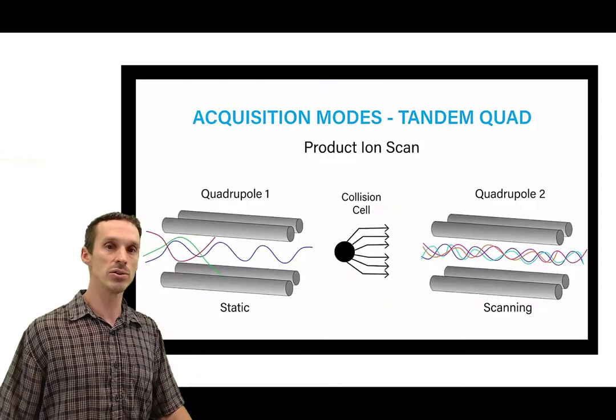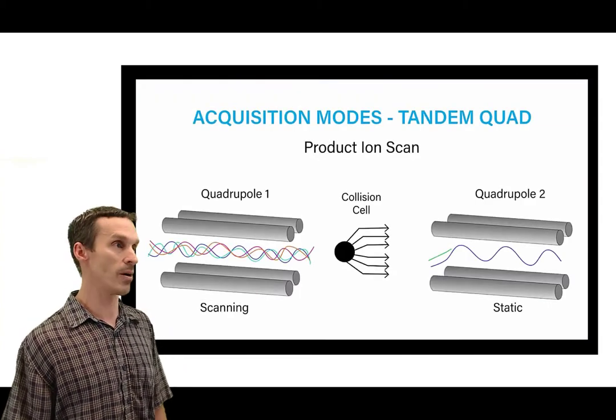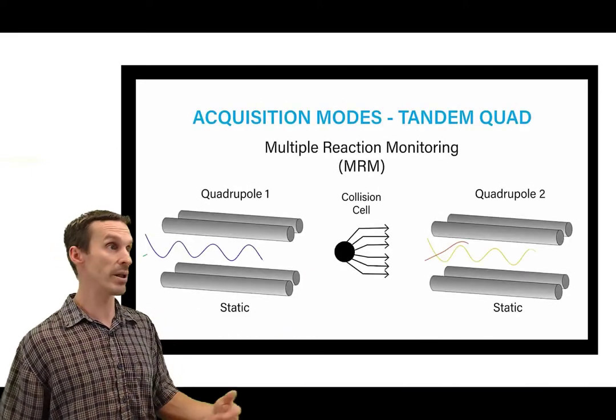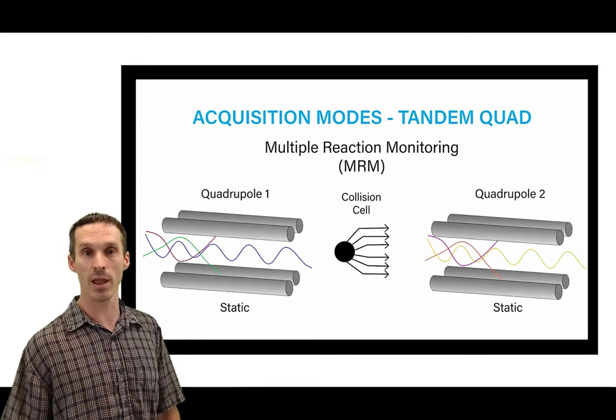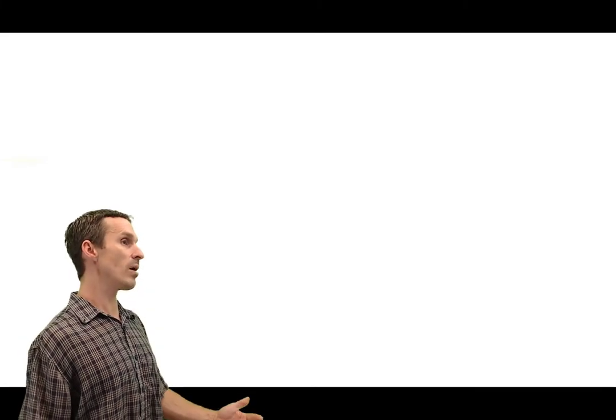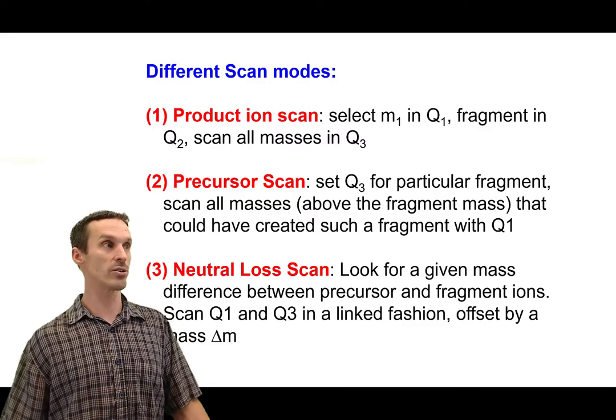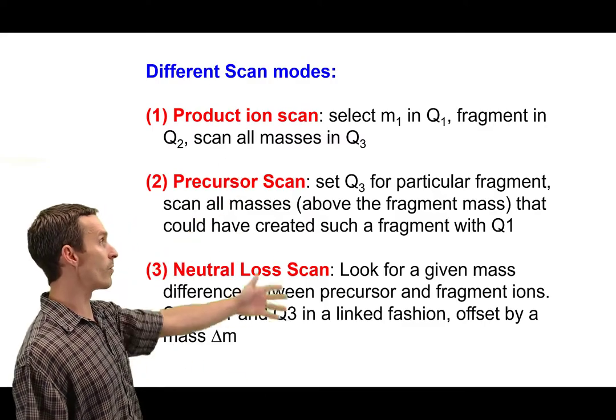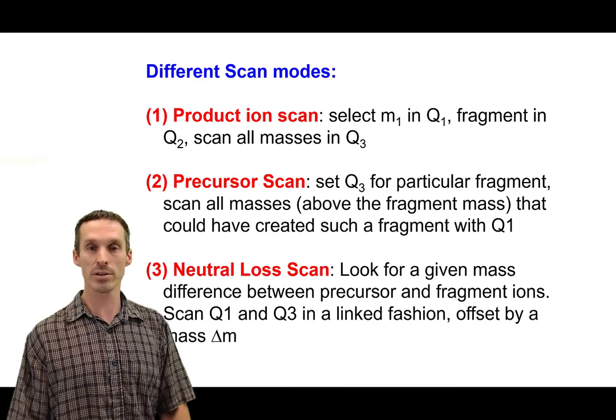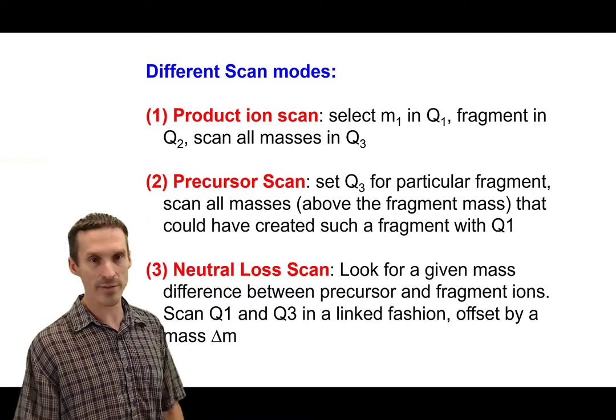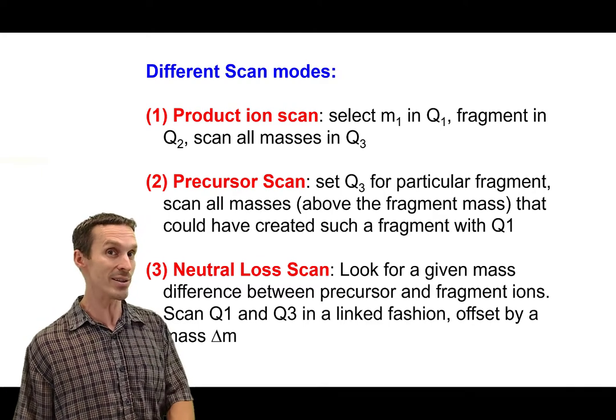With the triple quad you can do all kinds of different experiments. So you can do what we call a product ion scan, you can do neutral loss scans and then there's even more coming which we're going to talk about in the next video, the MRM scans. But for now I do want to go through the different types of scans that you can do with a triple quad instrument. Here they are, the product, precursor and neutral loss scans. So let's just go through them one by one. They're just subtle differences between them but they are quite distinct.